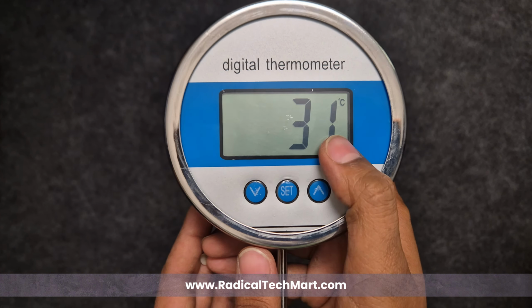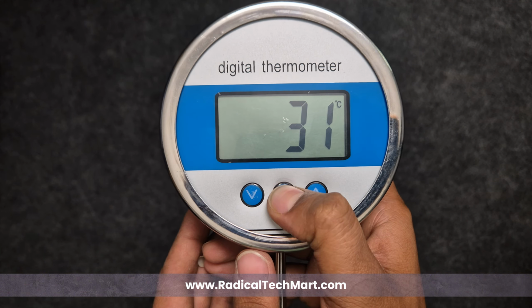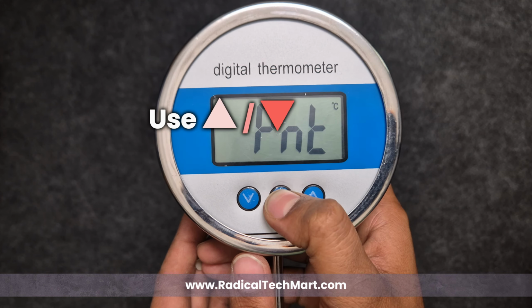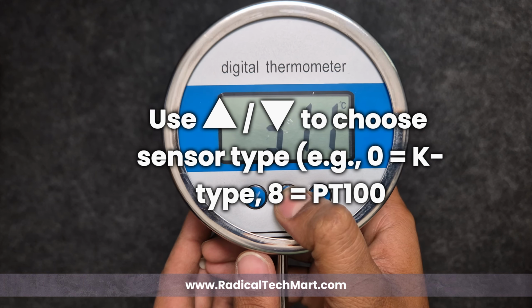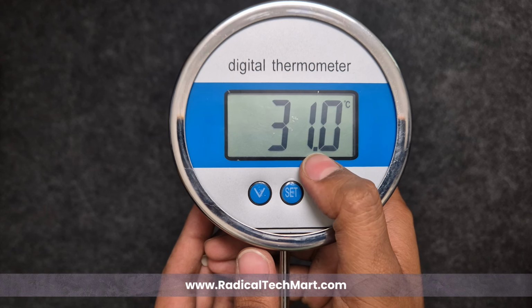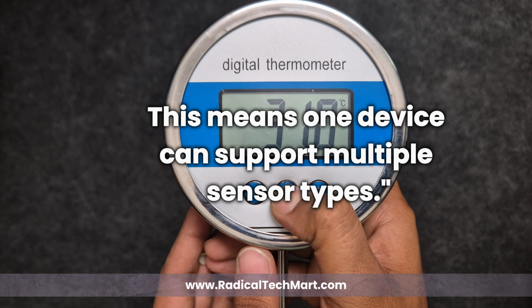Let's check sensor type selection. Long press the set button. In the menu, go to TYP. Use the buttons to choose sensor type. Example: 0 is equal to K-type, 8 is equal to PT100. Short press set to save. This means one device can support multiple sensor types.